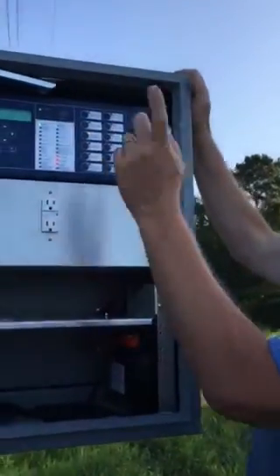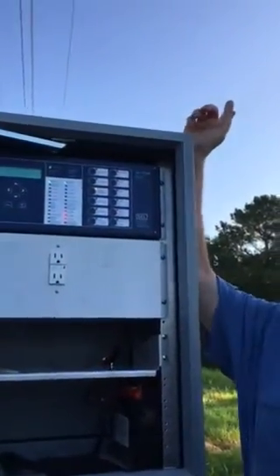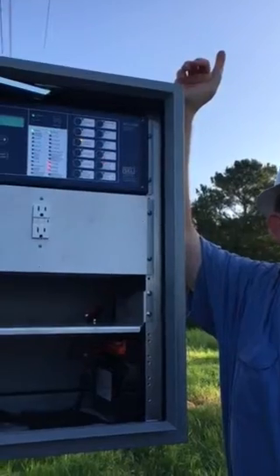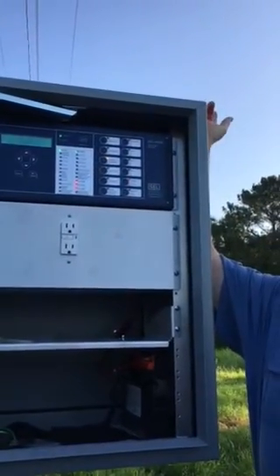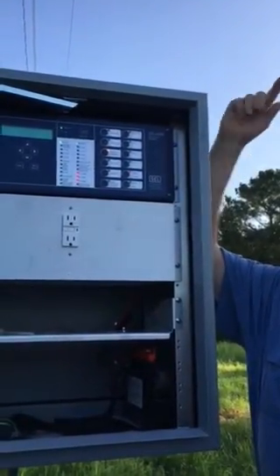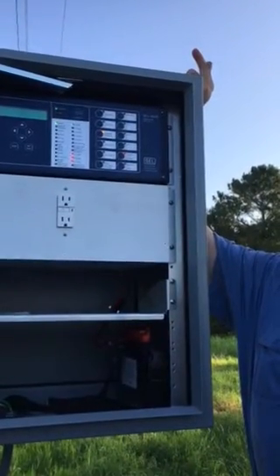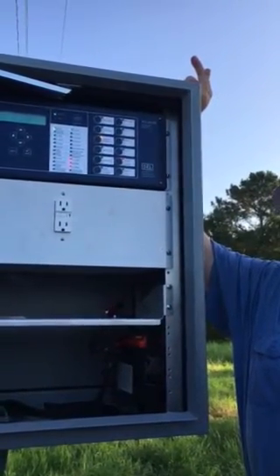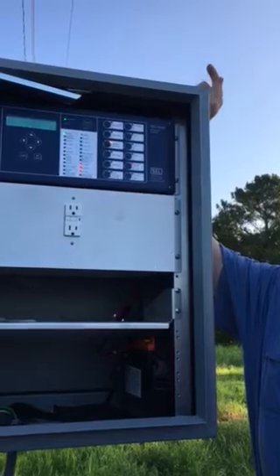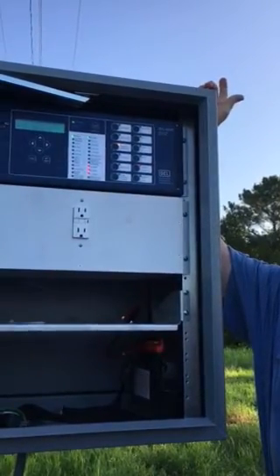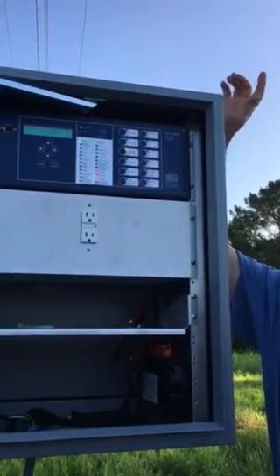If you have a fault come through, the way this thing is set up, it's watching from the solar field on the load side and from the station on the source side. Fault comes either way, this breaker's going to open. The load side from the solar field is set a lot lower, and I don't know what the settings are. Those come from engineering, but they got them figured out. So either way it sees a fault, it's going to take its solar field offline.